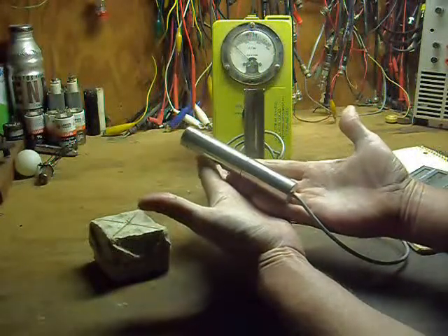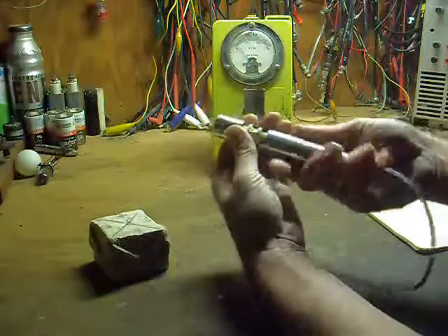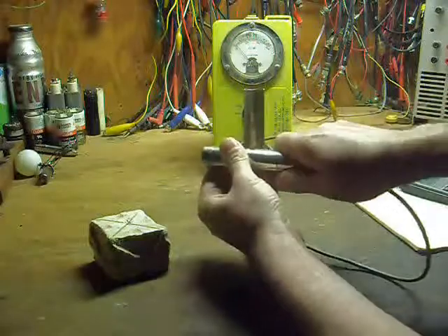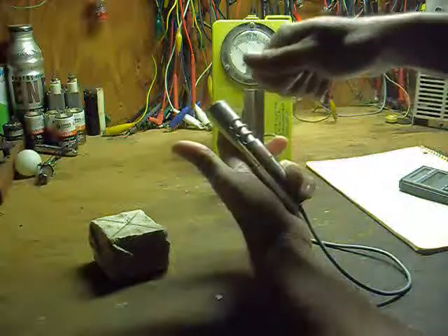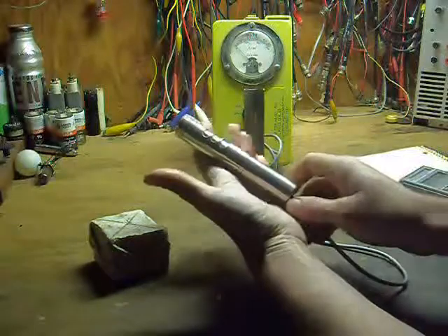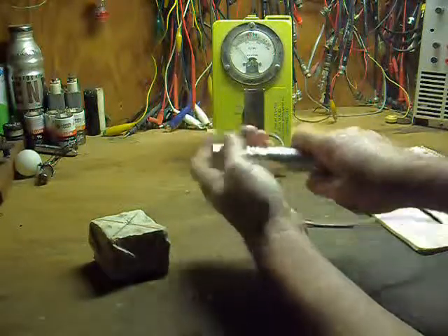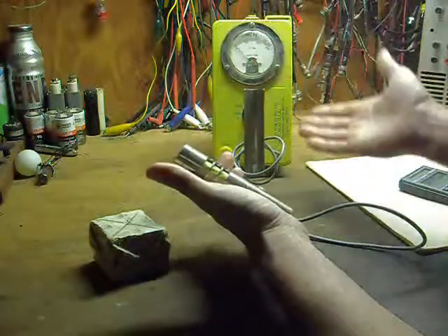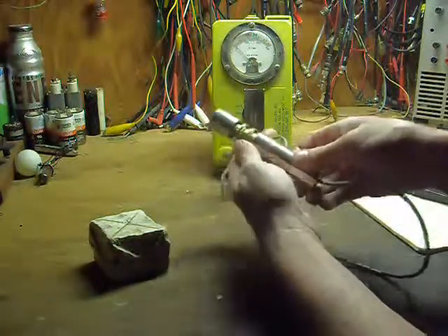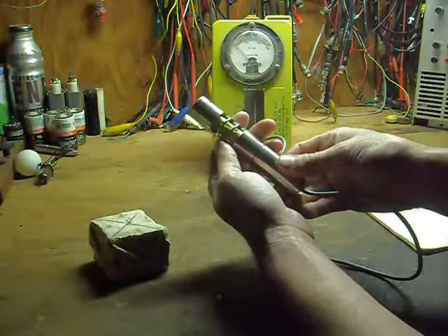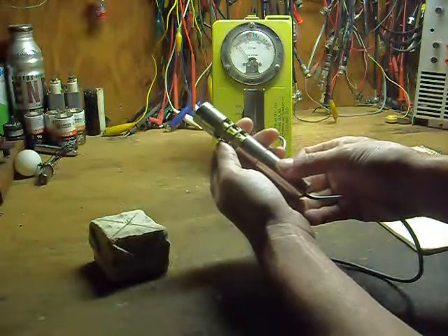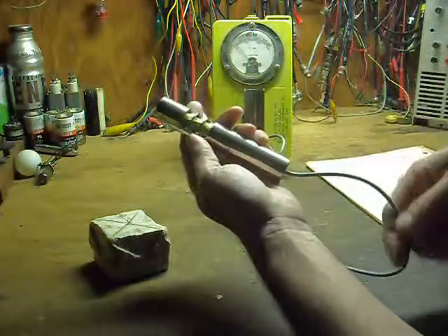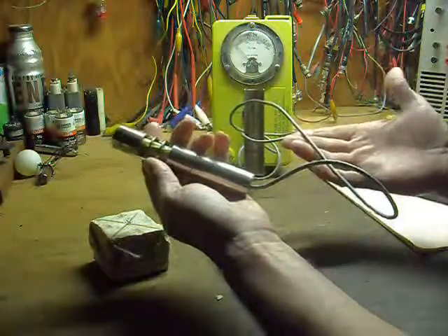The radiation detection probe has a movable window that can be opened to allow detection of beta particles. When closed, the detector is only sensitive to gamma and higher energy particles. The primary radiation detection element in the detection probe is a Geiger tube. That is why the entire instrument is called a Geiger counter. The Geiger tube is a gaseous discharge device. When an incident radiation particle passes through the tube, it produces a gaseous discharge which generates an electrical output pulse.